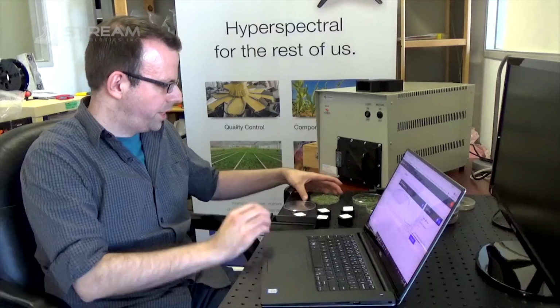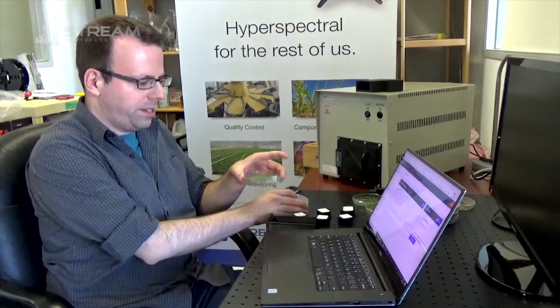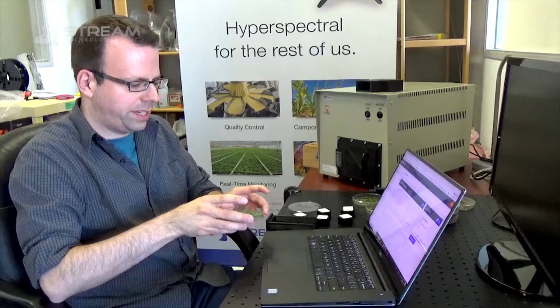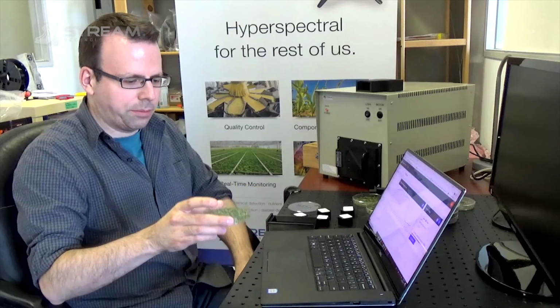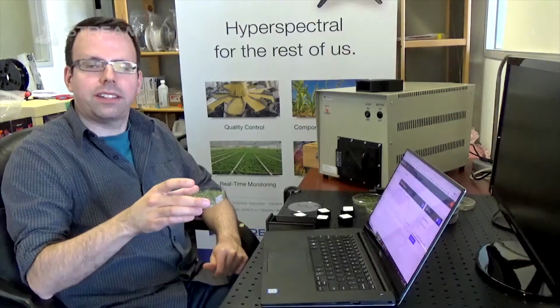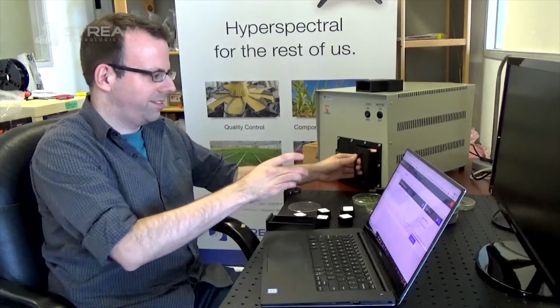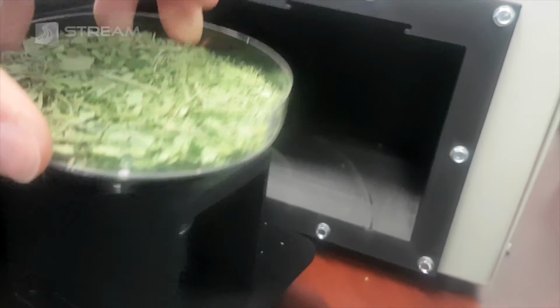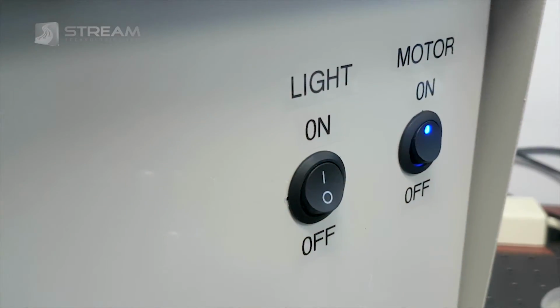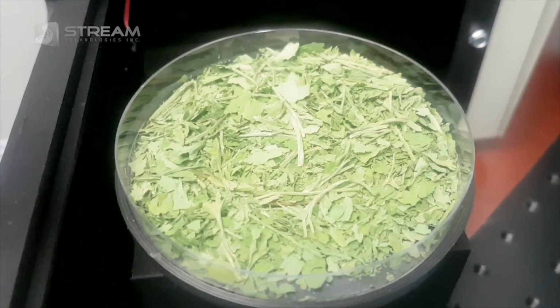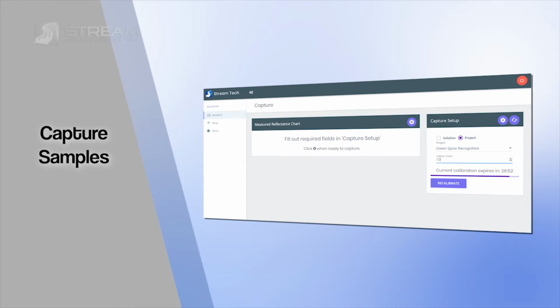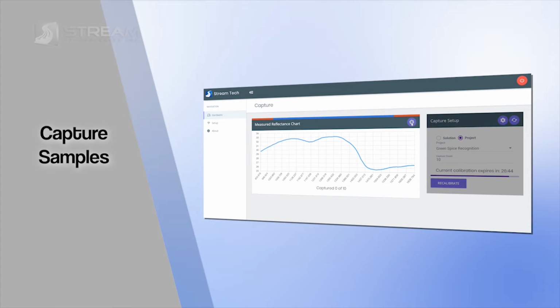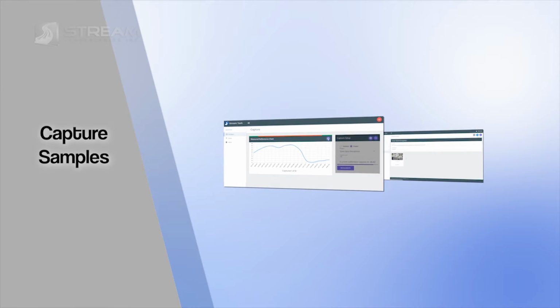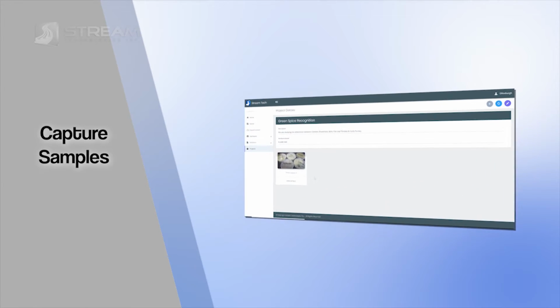I'm going to just take a sample here, which is some mint, basically. We've trained on mint and several other herbs. And I'll put that into the LabFlow and measure it, and we'll see if the LabFlow can identify that it's a sample of mint. And since we're doing more than one scan, we'll want to turn the motor on so that this spins the sample. And I'll just hit the capture button in the main capture window. And it will take our 10 scans. Once those 10 scans are done, they'll be uploaded to the cloud, and we can have a look on the main analytics website to see what our results are.